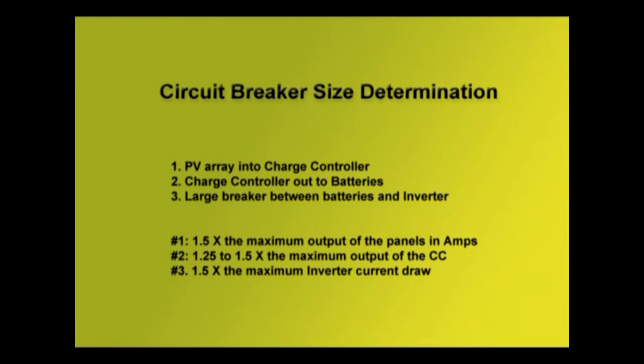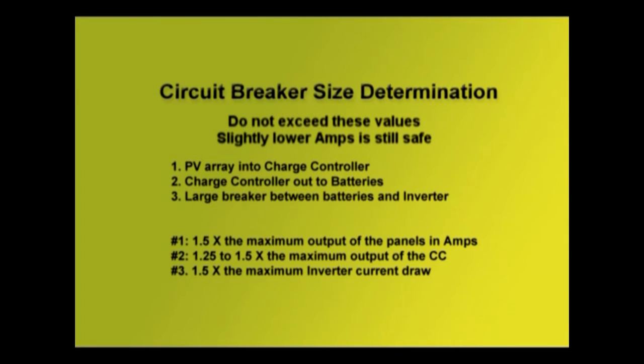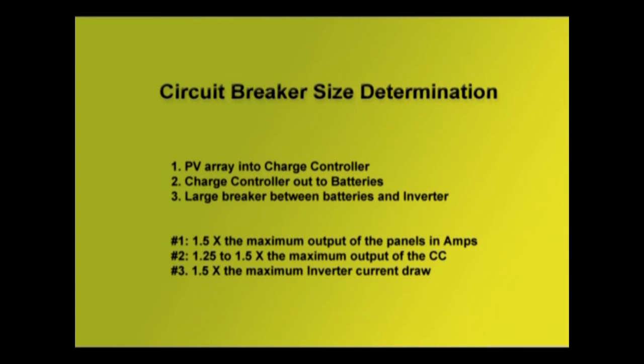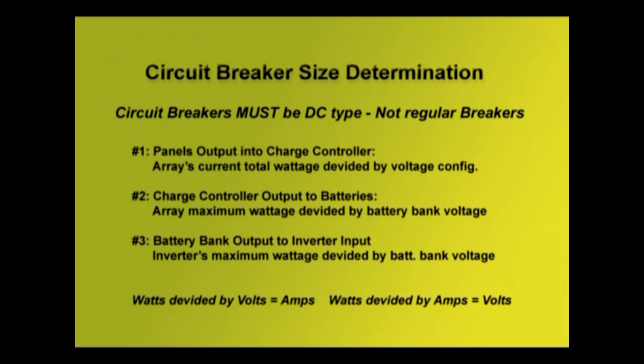Number 2, the charge controller output to the batteries for charging, 1.25 to 1.5 times the maximum output of the charge controller. I'm going to show you how to calculate these. You can go a little bit less on this one because it's not going to swing quite as much. And then number 3, the large one, 1.5 times the maximum inverter current draw that you can ever expect. Now let's take a look at how we calculate these. The first thing I want to say is these circuit breakers must be DC type, not regular breakers you get from a home improvement center or electrical contractor center. You'll need to order them special from a solar supply house. They're going to cost a little bit more, but you must use this type.